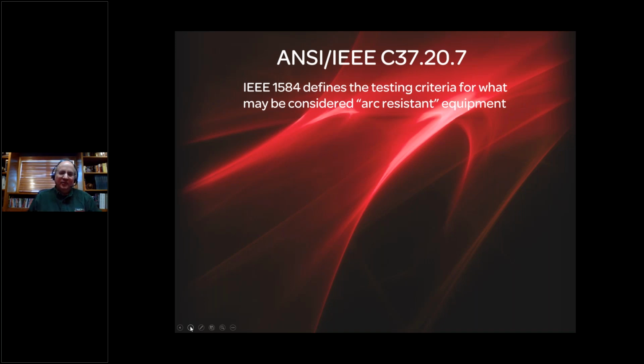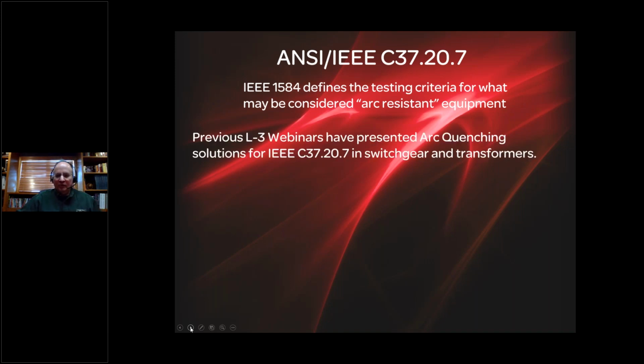Jumping into this presentation before you've seen our complete arc quencher presentation, which you can see linked on the L-3 website, might be confusing to you because we don't go deep into arc quenching technology in this presentation. We're here to focus on IEEE C37.20.7 compliance, particularly as it applies to variable frequency drives. We have given webinars in the past on incorporating arc quenching devices, turning equipment to be arc resistant. And whenever I say arc resistant, I mean compliant with IEEE C37.20.7. And we've done that for switchgear and transformers.